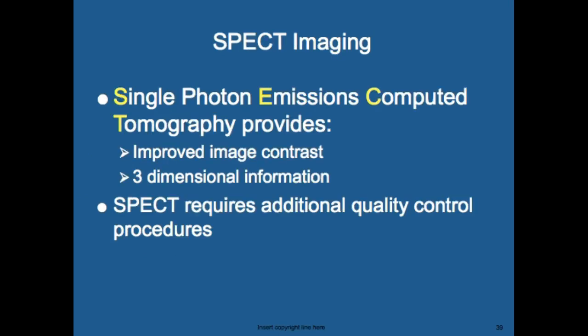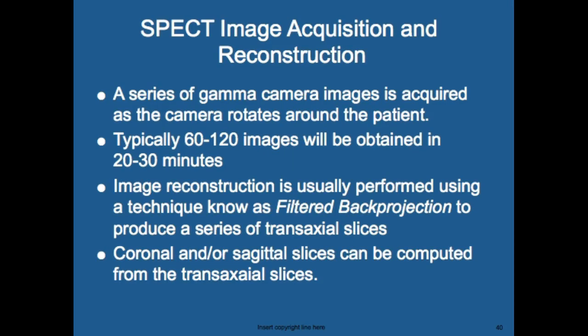SPECT — single photon emission computed tomography — provides improved image contrast and three-dimensional information. It requires additional quality control procedures and is a specialty scanner. A series of gamma camera images is acquired as the camera rotates around the patient; typically 60 to 120 images are obtained in 20 to 30 minutes. Image reconstruction uses filtered back projection to produce transaxial slices, and coronal and/or sagittal slices can be computed — similar to CT reformatting.